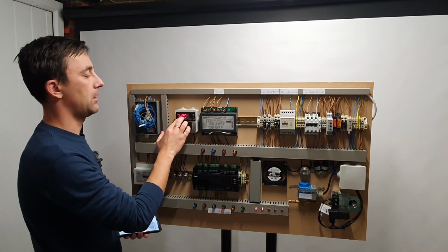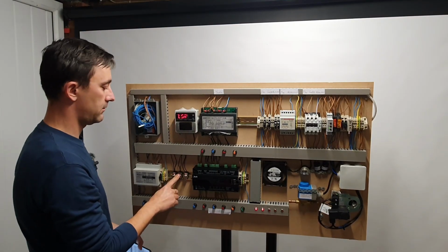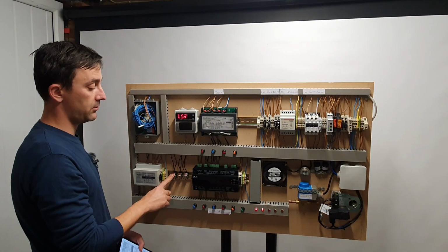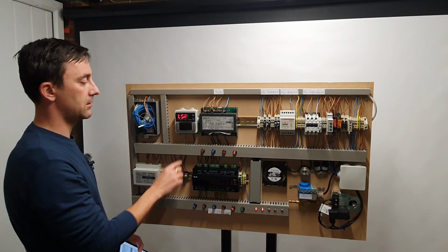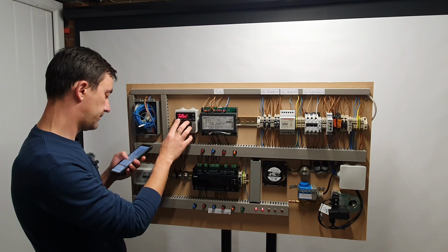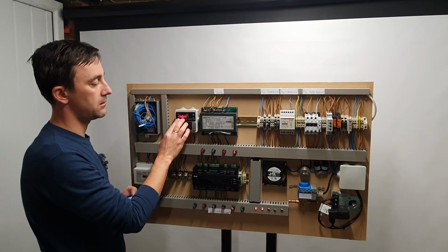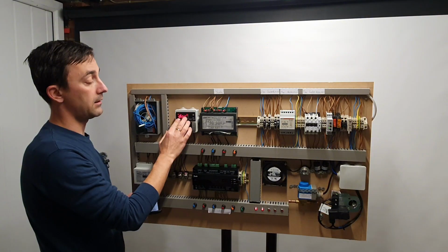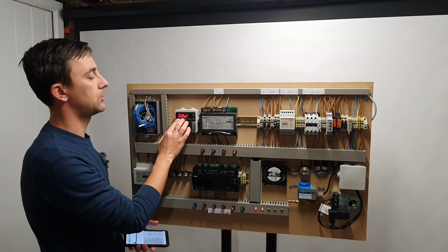Digital input 2, high pressure switch, yes. This would be my second one, which I talked about in a previous video. So this first switch is my door switch, and this is a simulation of my safety circuit switch. LSM, light switch mode, manual. Yes, you can set this as non-existent, manual, or the light comes with the door being open, but we're just gonna go with manual.